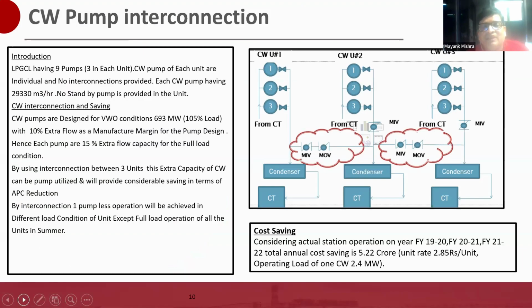We have provided CW pump interconnection. Nowadays in the design we have a lot of margins, and one of the margins we noticed is that the flow requirement for generating condenser vacuum in the condenser can be fulfilled with less than the designed pump operation.